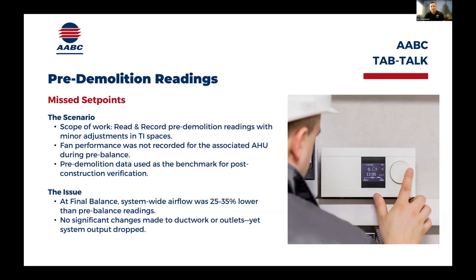One of the issues we brought up was missed set points. I had a story of a project similar to many of yours. We had a specific space, and the scope of work was just diffuser inlet and outlet readings in a hospital. They gave us the highlighted area and told us to read all the diffusers in it. The back end, the post-balance or final balance, was going to involve two rooms that were modified, needing small adjustments, probably under 100 CFM total for each room. We went and measured all our pre-balance readings, establishing the baseline.